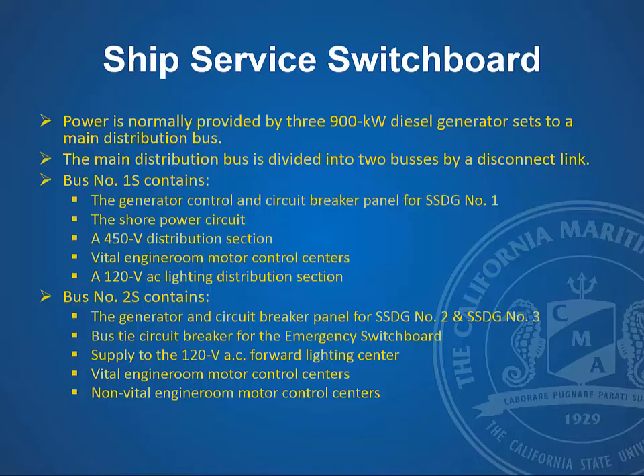So, bus number 1 contains the generator control circuit breaker panel for diesel generator number 1, your shore power, 450 volt distribution section. It has vital engine room motor control centers and 120 volt AC lighting distribution section. Bus number 2 has number 2 and 3 generators, the bus tie circuit breaker for the emergency switchboard, supplied 120 volt forward lighting center, and some vital engine room motor control centers and also non-vital motor control centers.